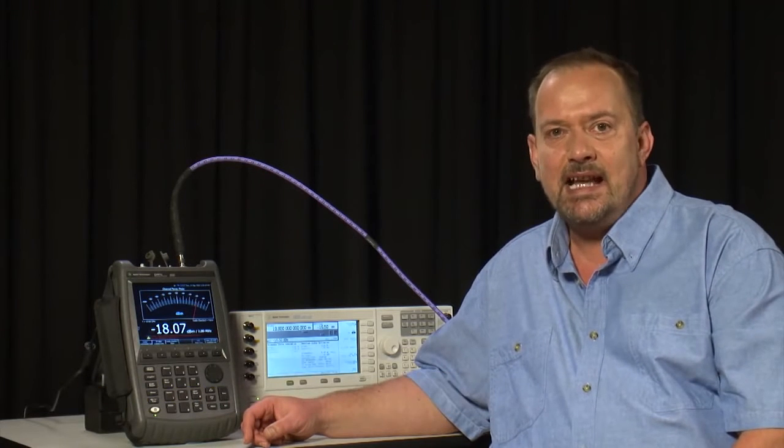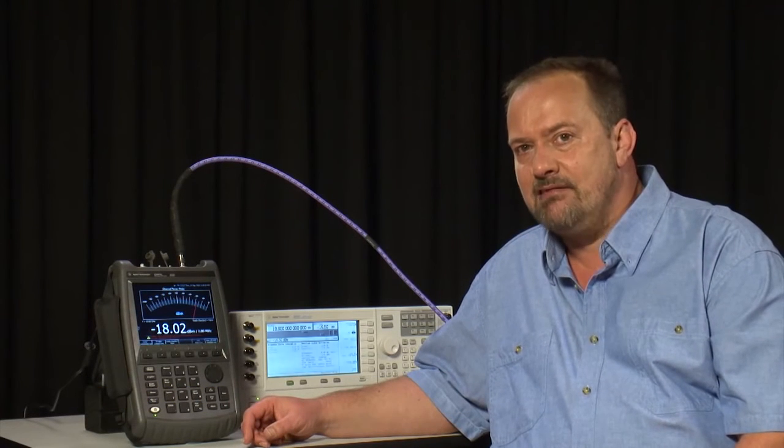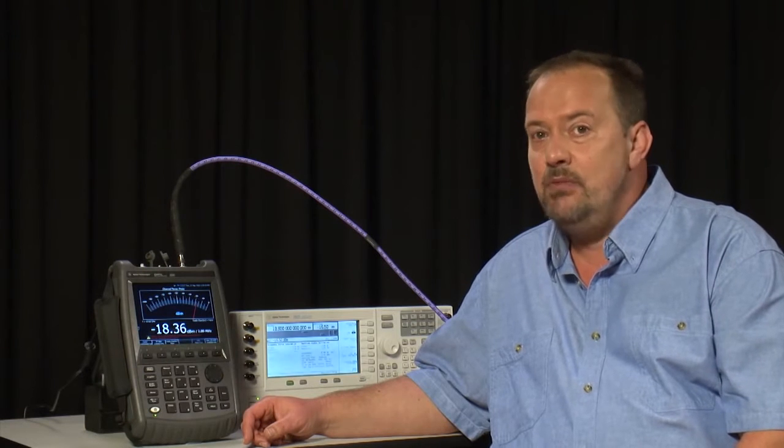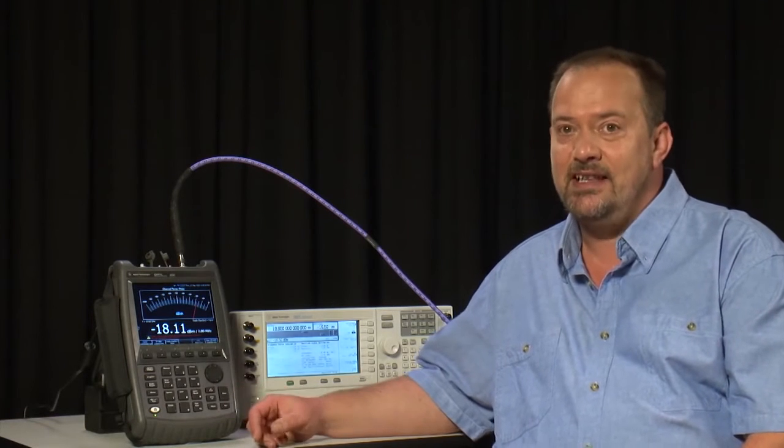The built-in channel power meter option on the FieldFox is very simple but incredibly useful, as it makes amplitude measurements with comparable accuracy to a real power meter but without the need for an external power sensor.